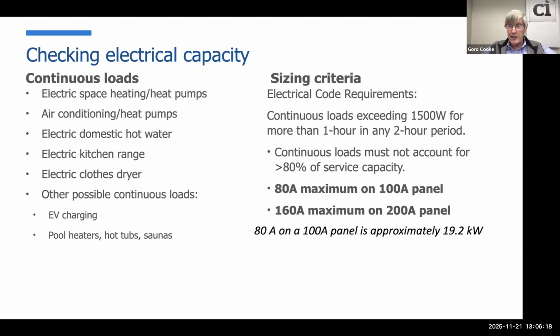First and foremost, though, we'd want to check our electrical capacities. We'd want to look at the continuous loads, the big loads, the electric space heating, the air conditioning, domestic hot water. Basically, most codes, I won't speak to Connecticut codes, but most codes would say take continuous loads that are more than 1,500 watts for more than 1 hour in any 2 hour period. You would understand water heating, kitchen range probably falls in that category. And typically, historically, you had designed your panel to meet 80% of that load, couldn't exceed 80%. So for example, in a 100 amp panel, you couldn't be using with those continuous loads more than 80 amps, on a 200 amp panel, 160.